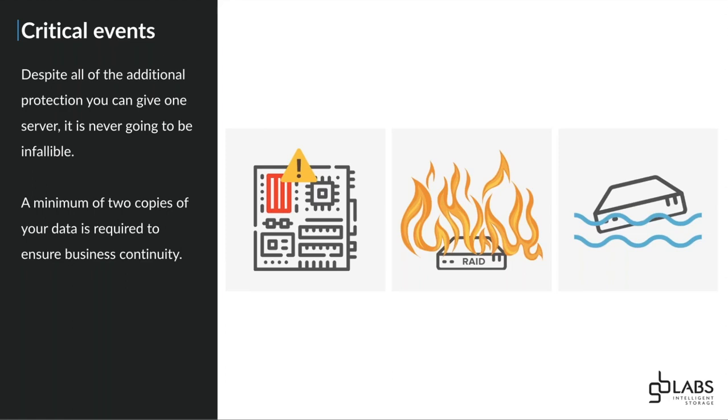In fact, in the past, you think you can predict all of these things ahead of time, but there was a large broadcaster in the UK who had a particularly large storage system and were very happy working away from this, thinking their data was very well protected, which of course it had: dual RAID controllers, dual power supplies, all of the things that we would normally expect. However, the gas suppression system fitted to the server room, which was there to reduce the oxygen in the server room, was being serviced, and unfortunately an accident occurred which allowed one of the cylinders to bounce and go through a ceiling, whilst at the same time the incredibly well placed jets or nozzles for the gas system sprayed ice cold gas straight into the front of quite a few RAID chassis and instantly stopped all of the disks.